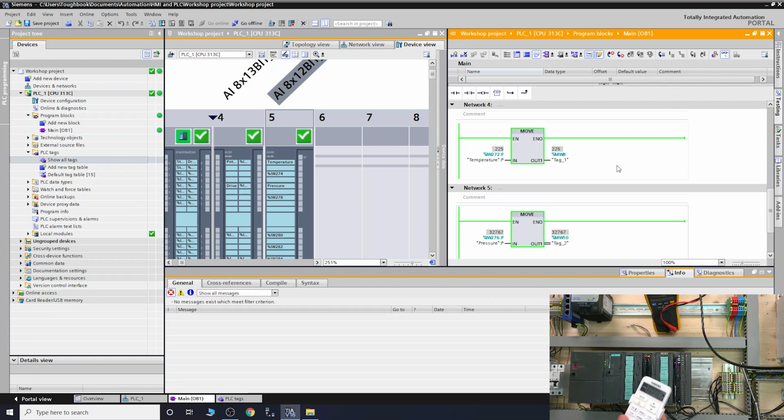So if you see in the camera, like in a window in there, that's pretty much as you can see, about 22 degrees, and it displays 225, so that's roughly 22.5 degrees. So that's for this channel, and that's literally how the PT100 wiring is done with a 7KF01 or /02. So let's jump quickly on to the 1KF card because it's done a little bit differently. So you jump on that and let's check that out.